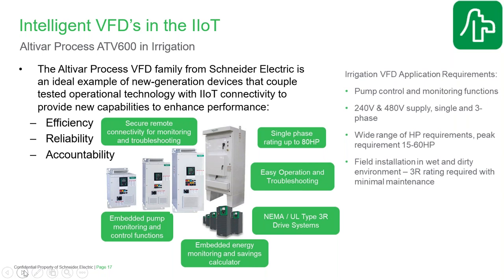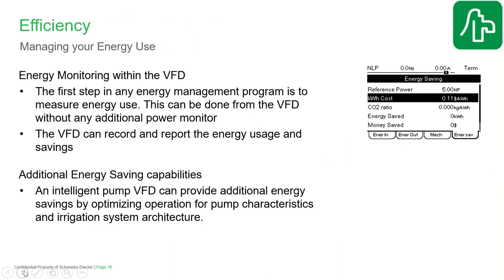The idea is that this enables us to increase the efficiency, the reliability, and the accountability of the application system. And what does that mean in real terms? Well, if we're looking at efficiency, first of all, with smart pumping, we're talking about saving energy and managing energy. The first step in managing energy is measuring energy. Built inside the VFDs are energy monitoring capabilities, and the drive can be used as a means of measuring and calculating how much energy you're using and trending that over time.